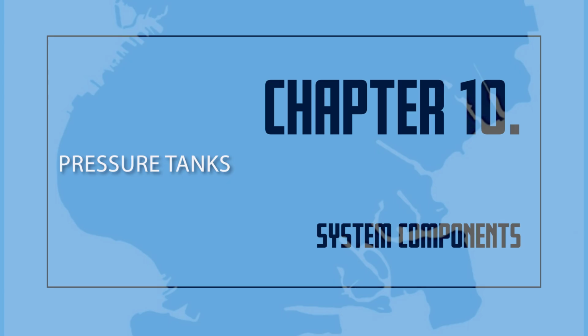Pressure tanks are to be maintained at approximately 2/3 full of water and 1/3 full of pressurized air. The minimum acceptable air pressure inside the tank is 75 psi. The air pressure in the tank is automatically maintained by an air compressor. The maximum gross capacity of pressure tanks is 9,000 gallons. Some sprinkler systems require more than 6,000 gallons of water. When this occurs, several pressure tanks are used in combination to supply the system.